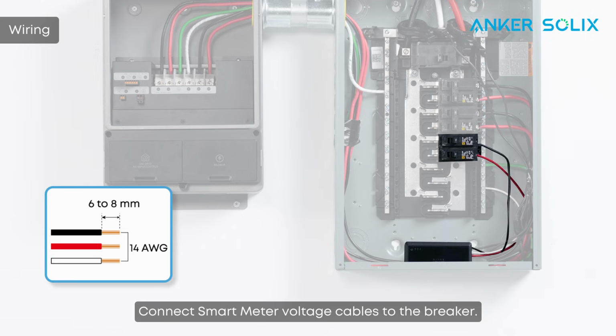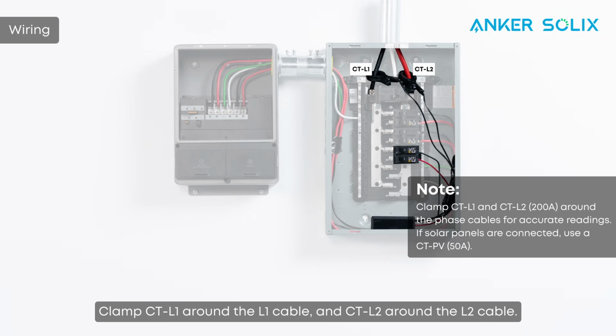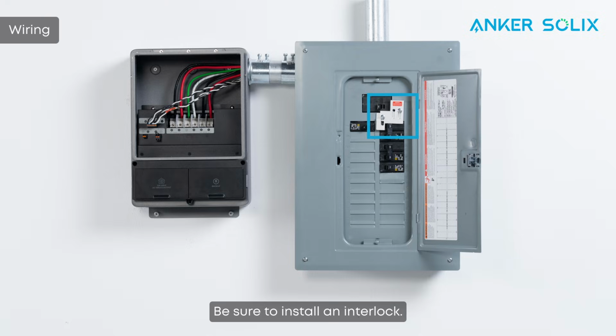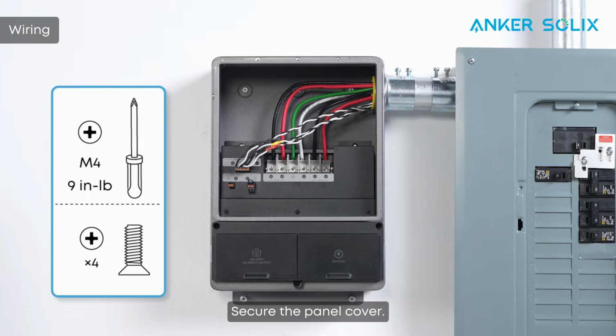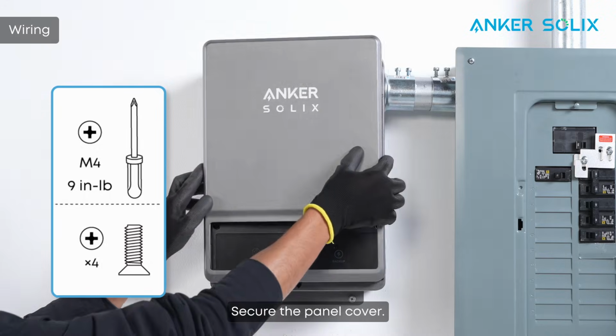Connect smart meter voltage cables to the breaker. Clamp CTL1 around the L1 cable and CTL2 around the L2 cable. Be sure to install an interlock. Secure the panel cover.